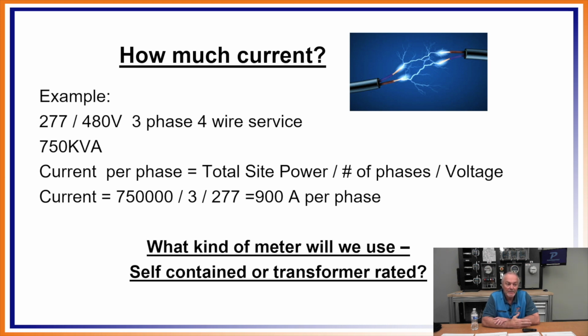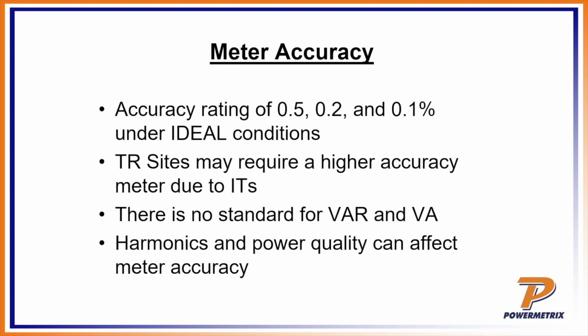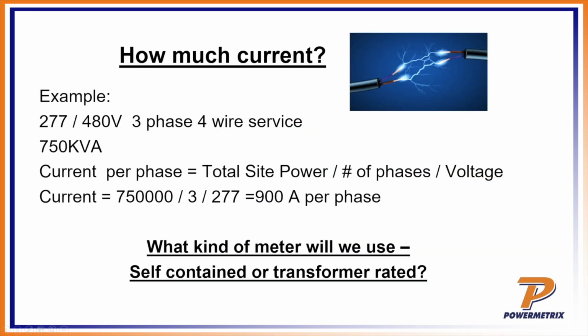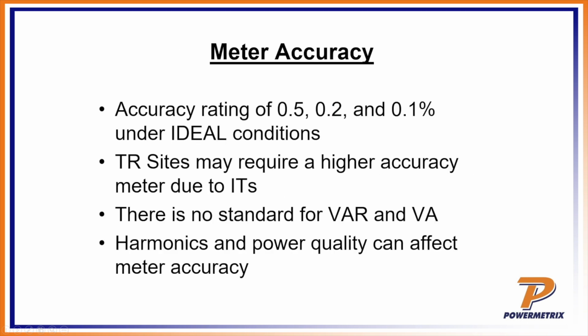So now what kind of meter will we use, self-contained or transformer rated? Remembering our limitations on the self-contained from the previous slide, you should say to yourself, I think I know the answer, because I'm over 600 amps, right? So you would have to go with transformer rated on that one. So let's look at the meter accuracy.